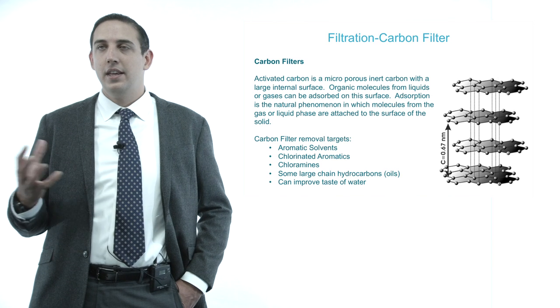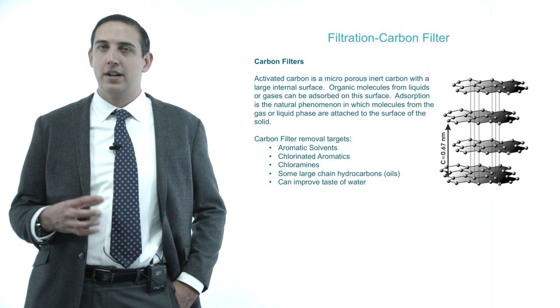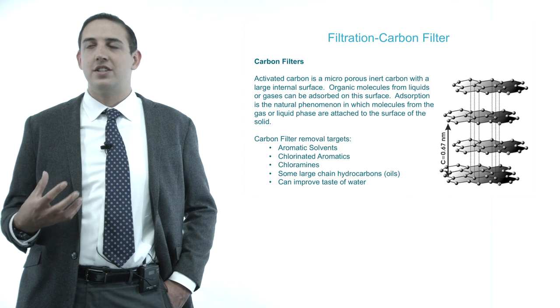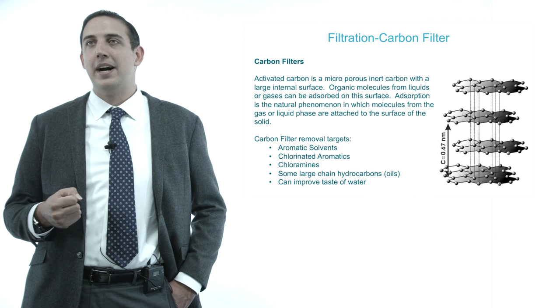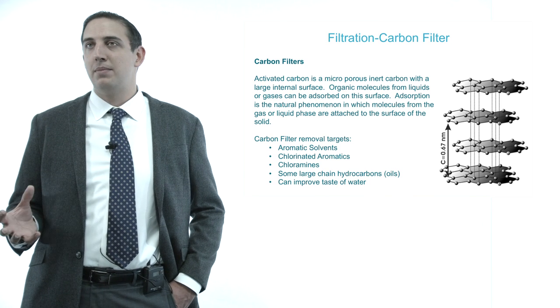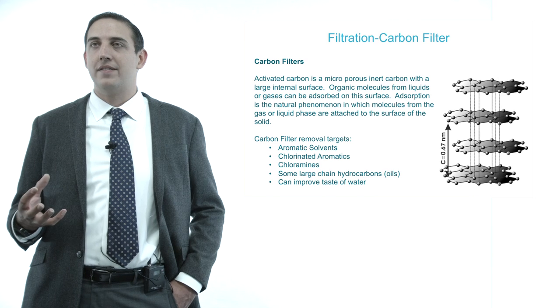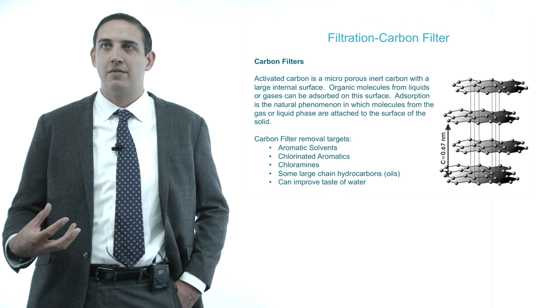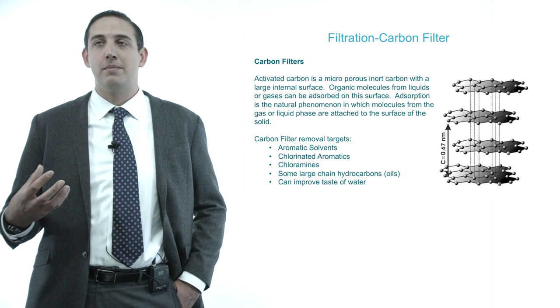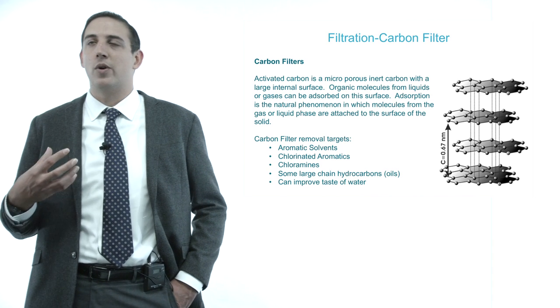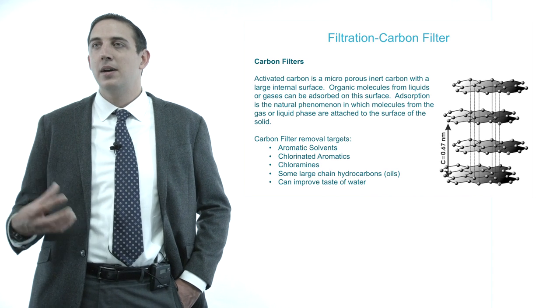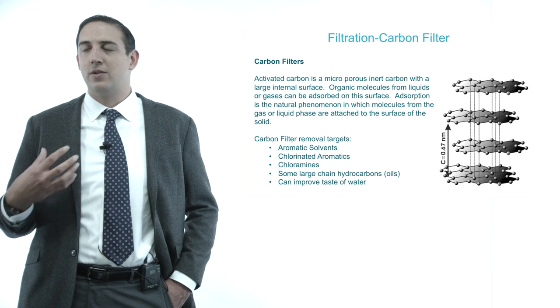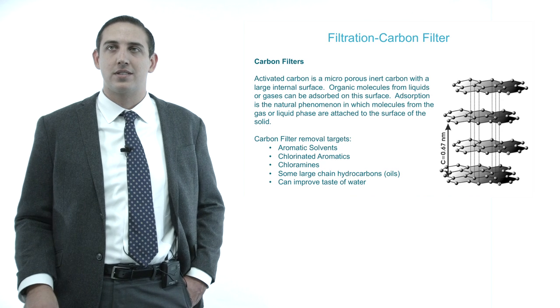Carbon filtration is sometimes utilized in rain and stormwater systems. Carbon essentially acts as a large graphite sheet that pulls out different organic compounds. This is a very case-by-case basis — you don't see a lot of organics built up in rainwater unless you have a very specific regional situation, or if you're treating for potable use where you'd remove aromatics to improve taste. Generally speaking, a carbon filter is not a necessary filtration step for rain or stormwater reclamation systems.